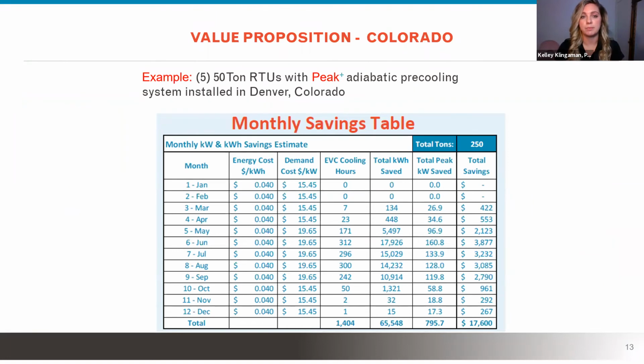Just to go over an example: 5 50-ton RTUs in Denver, Colorado, with our adiabatic cooling system in place. This is a savings estimate, broken down month by month using Xcel Energy tariffs, so we're giving you an accurate savings estimate. For these 5 50-ton units, we're seeing an annual savings of a little over 17,000 — a huge offset of costs for your building owner.